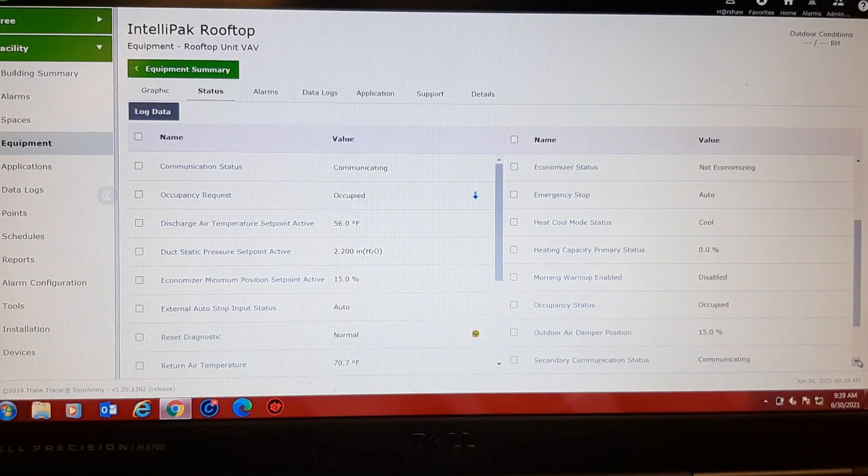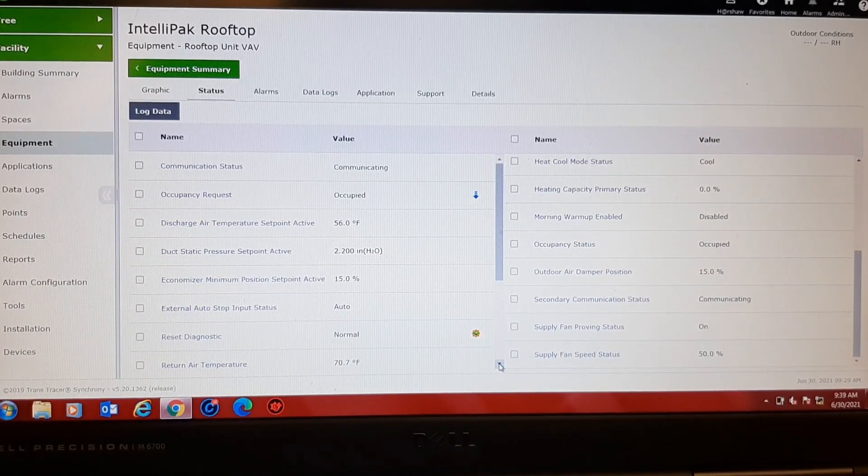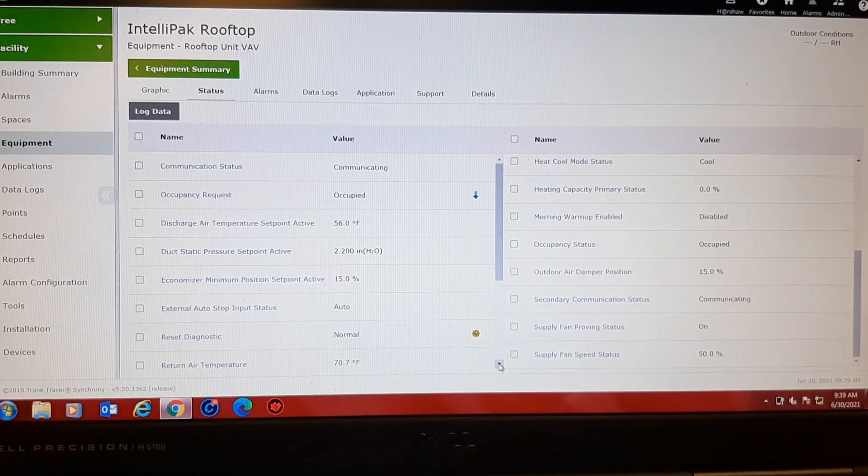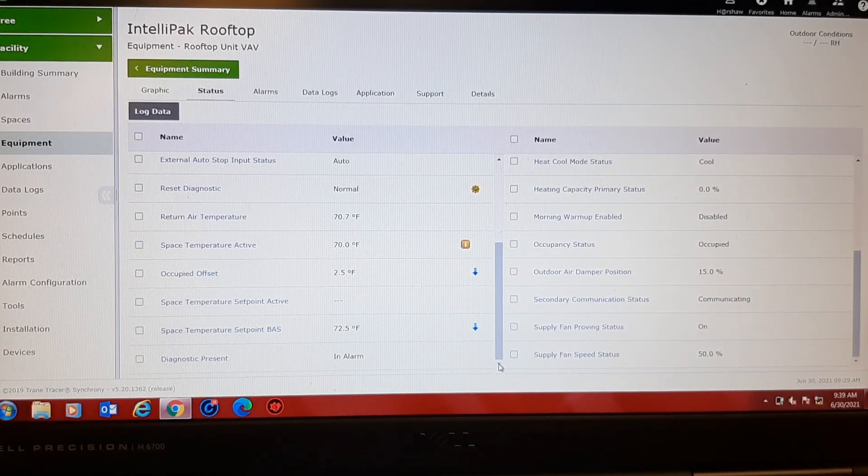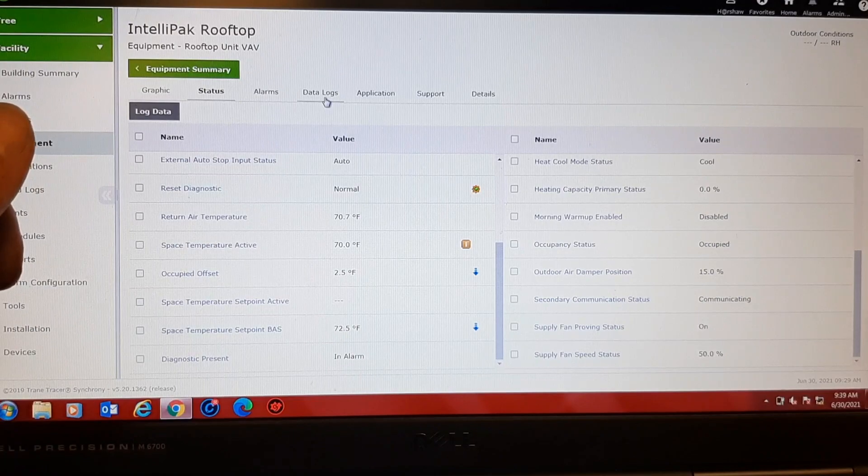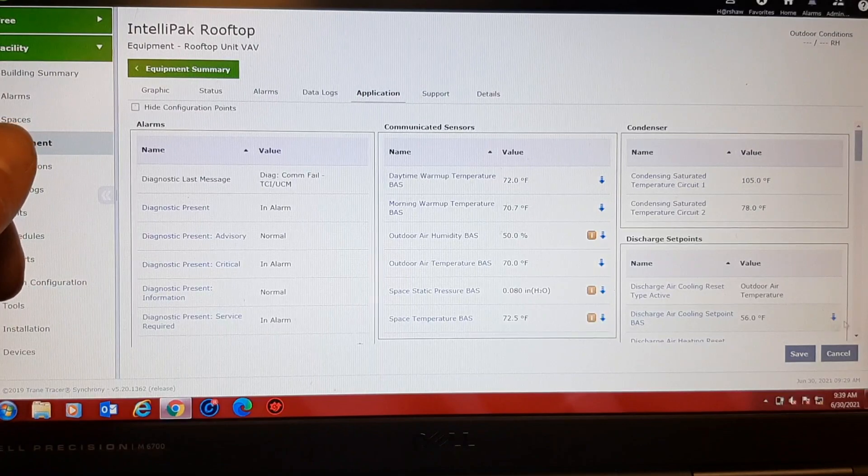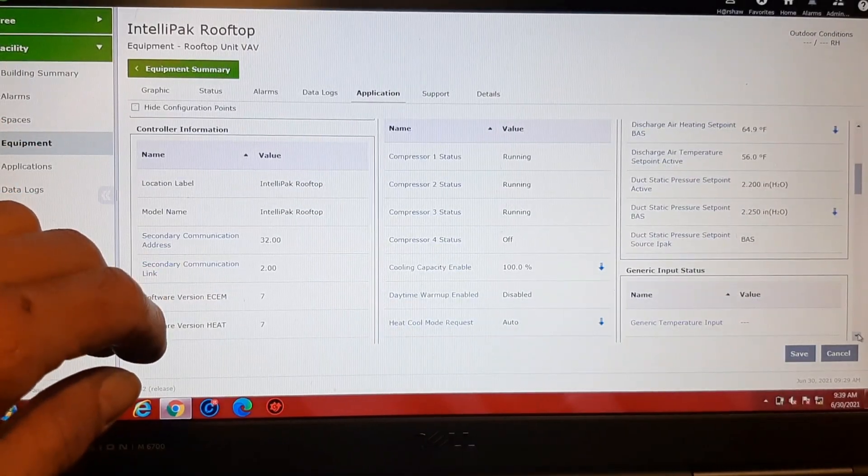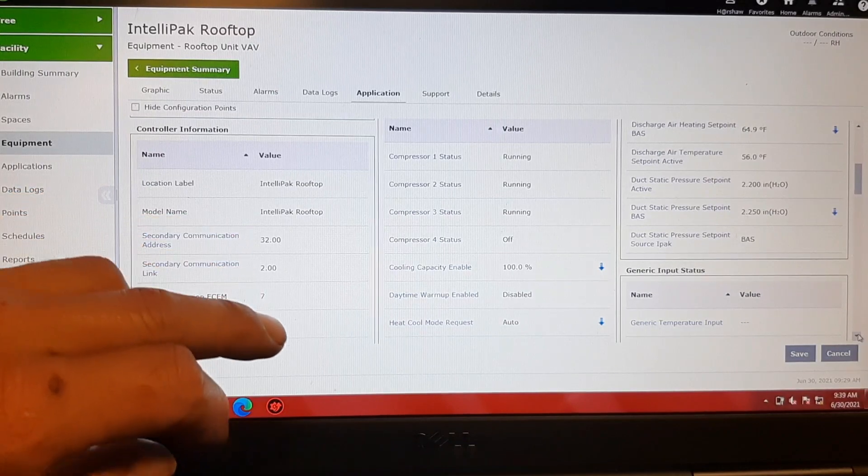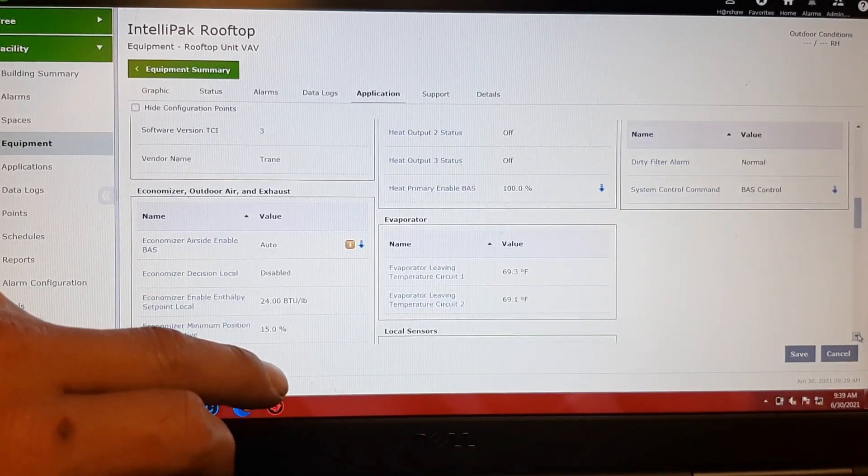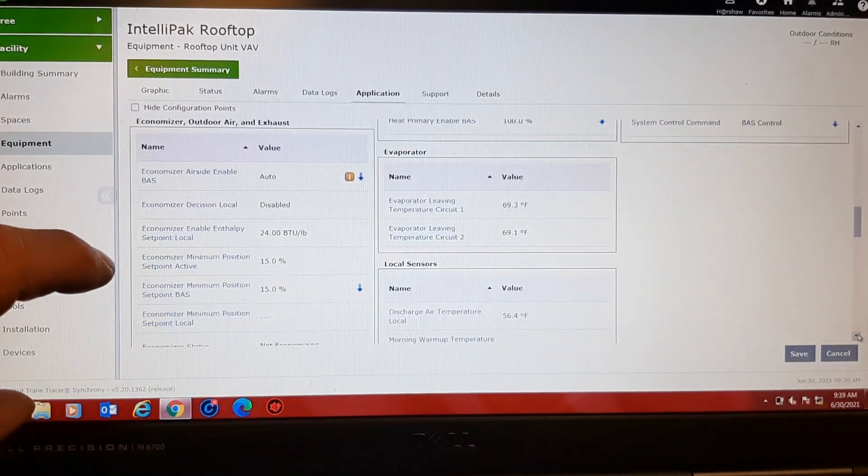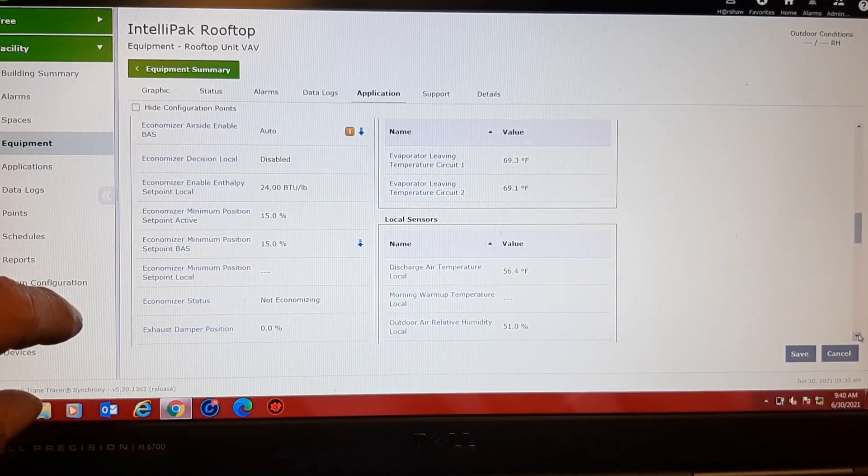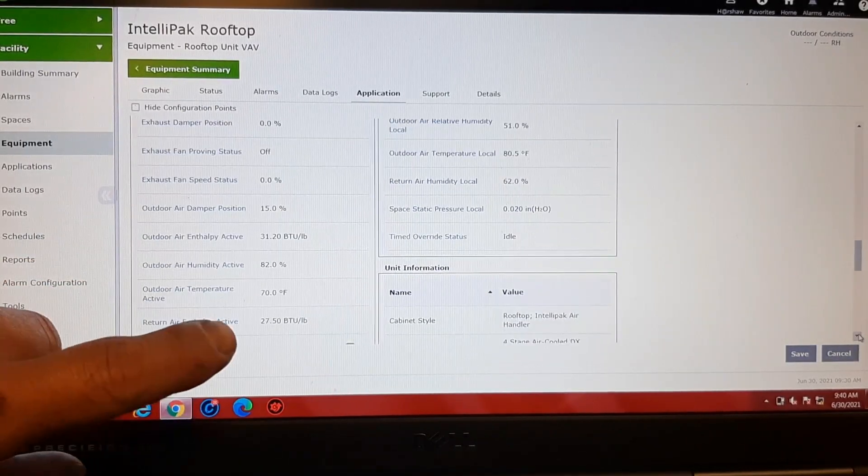And I'm wondering what it looks like. And we don't have a set point because we're not controlling off space temperature. Let's see if I can find out what my actual static pressure is, find out where that's at. I think I looked at it on the roof and it was normal. If y'all ever dealt with these, it depends on who sets them up and how they're set up. The stuff can be in different spots. It makes it kind of a pain, but other than that, I like these controls. Space pressure now is normal.